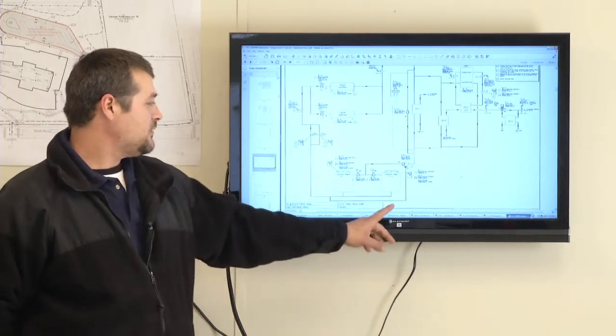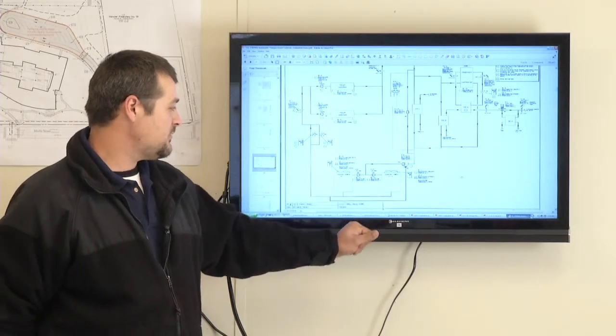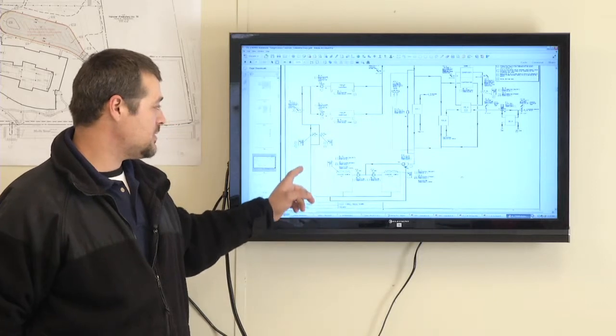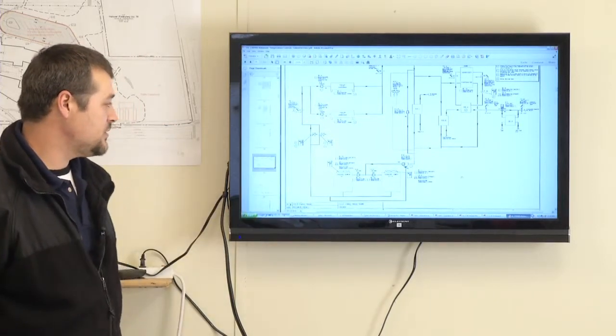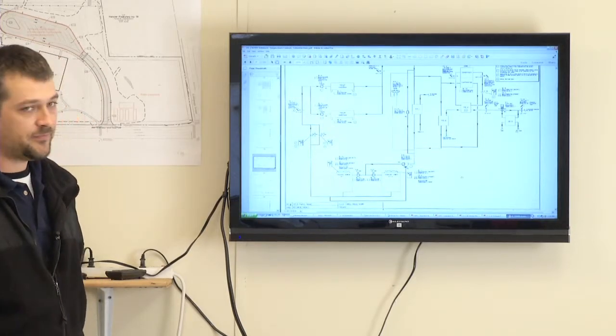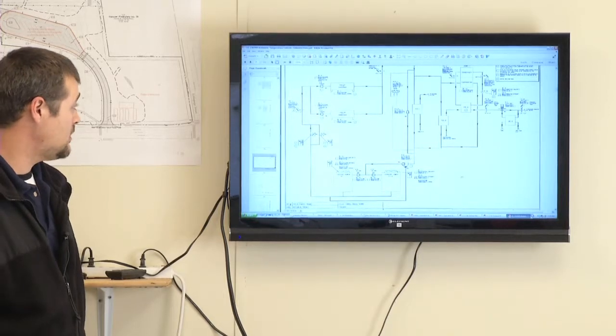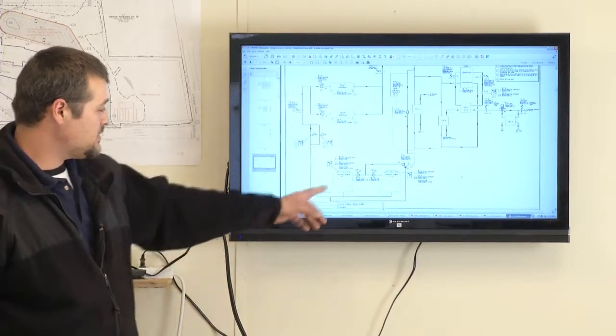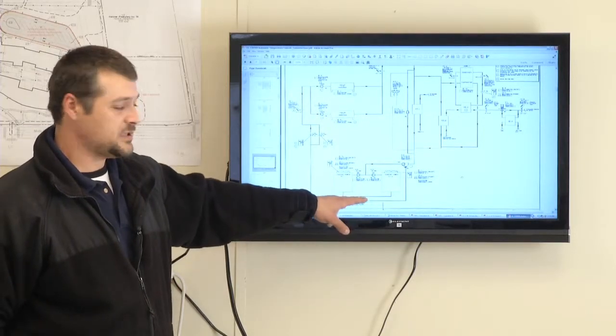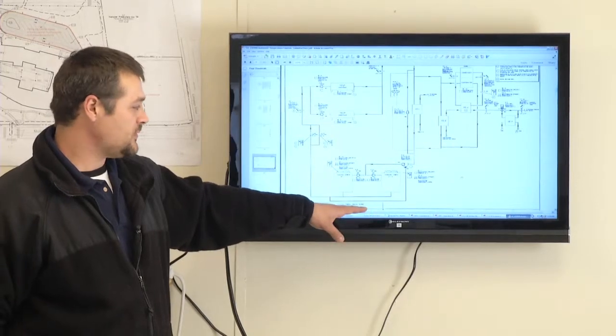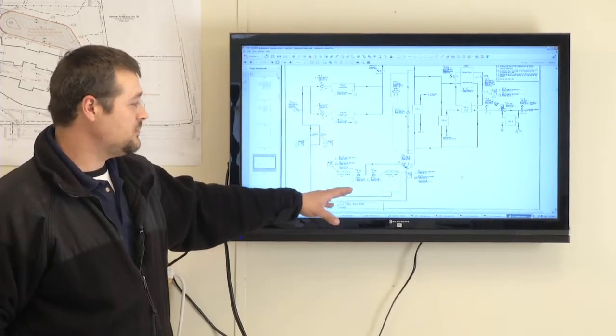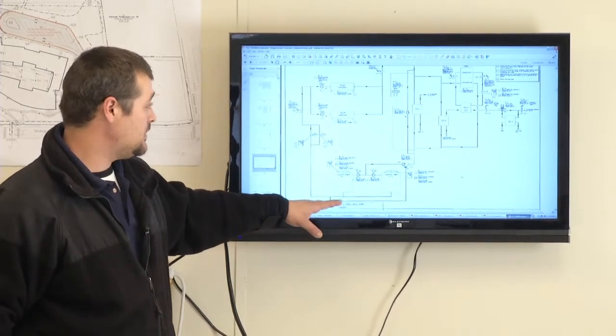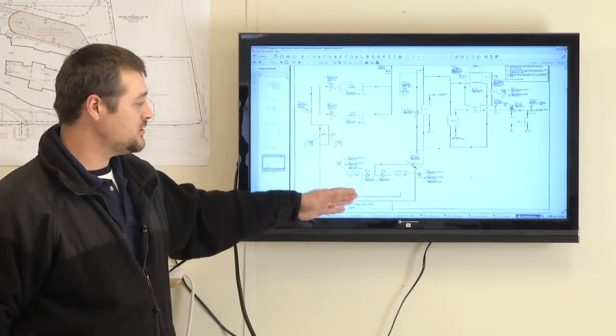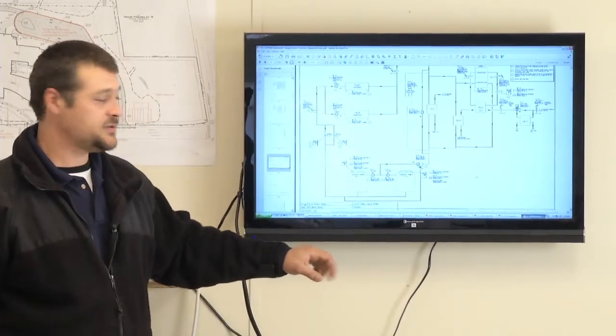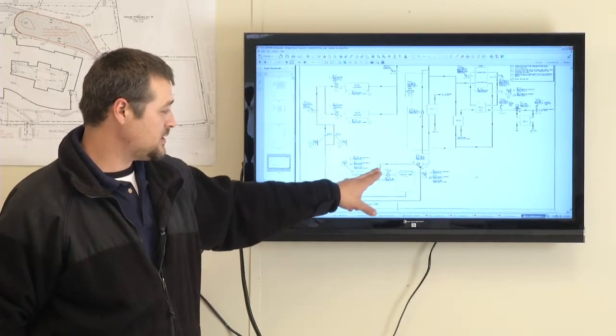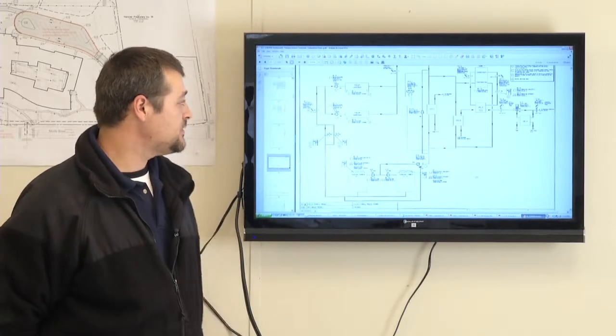When it comes to the bypass valve, I may not have mentioned this earlier, but this bypass valve operates to maintain a reasonable temperature deadband coming back into the chiller. If the condenser water is too cold, it can lead to mechanical failure, and if it's too hot, it can also lead to high limits, alarming the chiller and the chiller shutting down. So we'll bypass the cooling tower if it gets too cool. We also monitor the cooling tower fan speed. If the fan speed is elevated beyond the point where we assume that a high demand for cooling is active, we don't want to shut that valve down. So we will modulate that valve between 0 to 10 volts, going from a normally open position to the cooling towers at 0 volts to a full bypass at 10 volts.